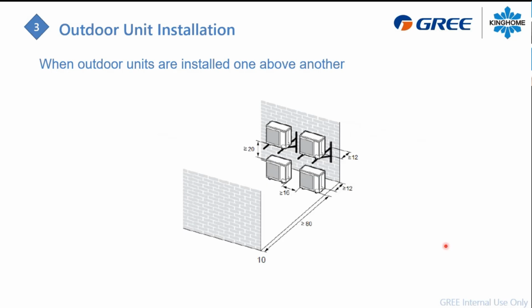If it's an installation above another one, you will have to manage the defrost. You will have some water falling from the top unit, so make sure you have enough space to manage that condensed water and not build a block of ice on the unit below.